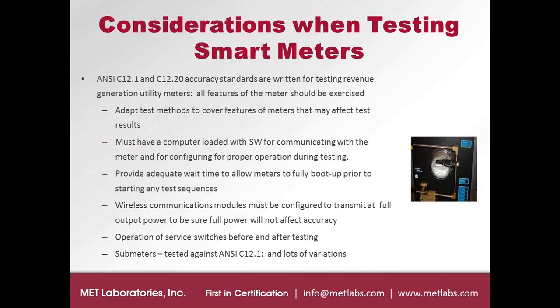When we're taking a look at what the sub-meter is and what the application is, we really have to be creative sometimes in coming up with a test plan that covers the criteria in the standard, but is tailored to what that sub-meter is all about. So that can be challenging at times, but we work with the manufacturer as well to come up with a solid test plan that covers all the features, but is not going beyond what the sub-meter is really designed for.